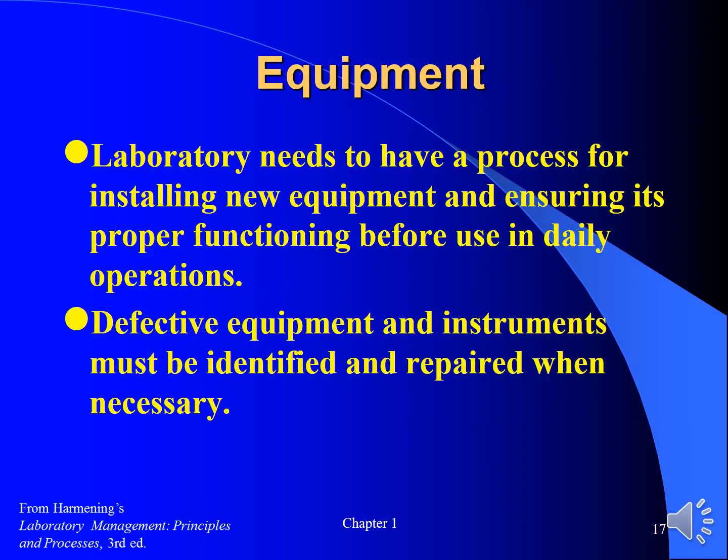The laboratory needs an equipment management plan that meets manufacturers', regulatory, and accreditation requirements. Laboratory records of all installation, calibration, maintenance, use, troubleshooting, service, and repair activities are required to be maintained for the life of the equipment's use and for specified times after decommission.